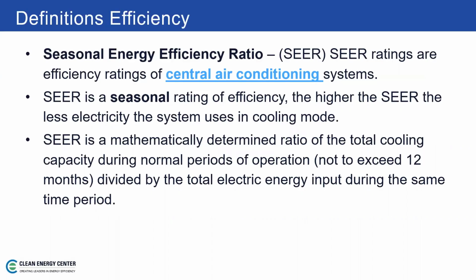Seasonal Energy Efficiency Ratio, SEER, is the rating of efficiency for central air conditioning systems. And even if it's a heat pump, it's really just the efficiency of the cooling side. It's a seasonal rating, so it's looking at the amount of energy that the unit uses over the season compared to the amount of BTU output that it has across the entire cooling season. The higher the SEER, the less electricity the system uses when it's in cooling mode. The SEER calculation is a mathematically determined ratio of the total cooling capacity during normal periods of operation, not to exceed 12 months, divided by the total electric energy input during the same time period. So again, it's just looking at the BTU output of this piece of equipment based on the amount of electric energy we have to put into it to run it.